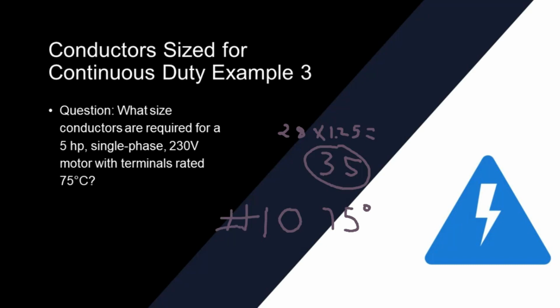I multiply that by 1.25. And what does that give me? 28 times 1.25 is equal to 35. So now I know 35 is my magic number. I'm going to run over to table 310.16 in the 75 degree column. And I should be able to put number 10s on there, right? Number 10s in the 75 degree column for 75 degree rated terminals. 75 degrees, so a number 10.